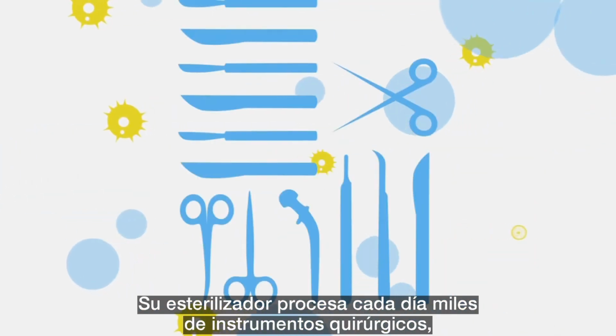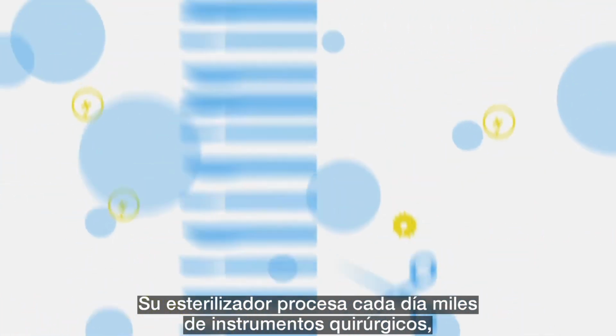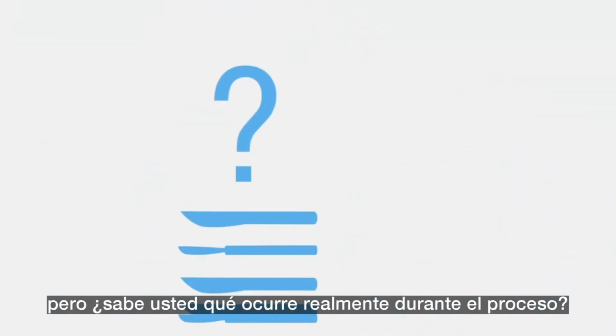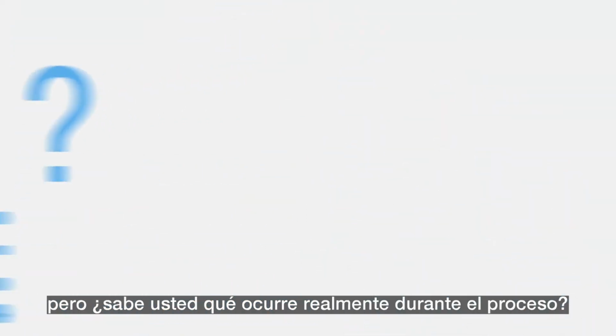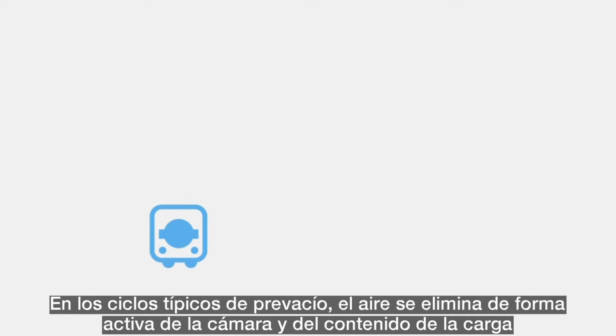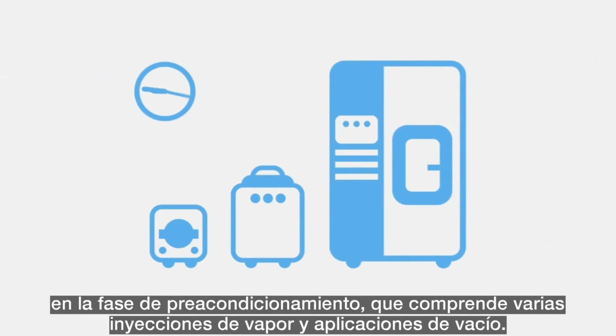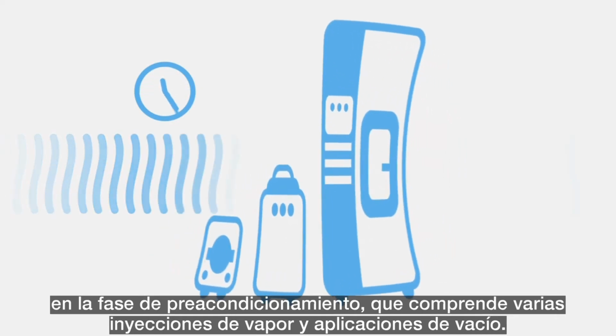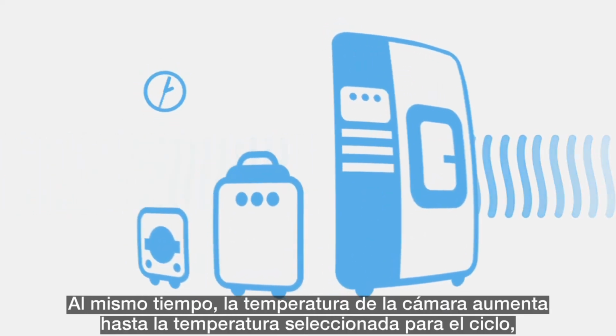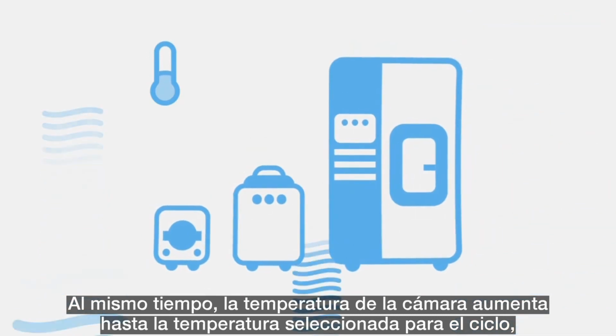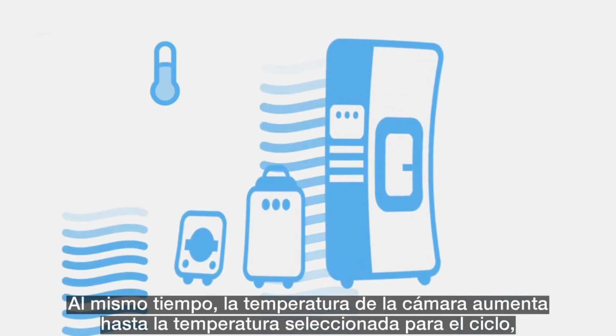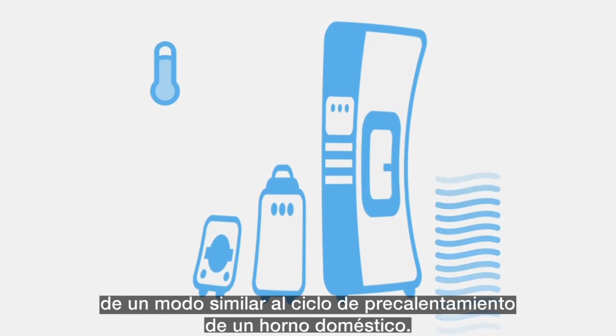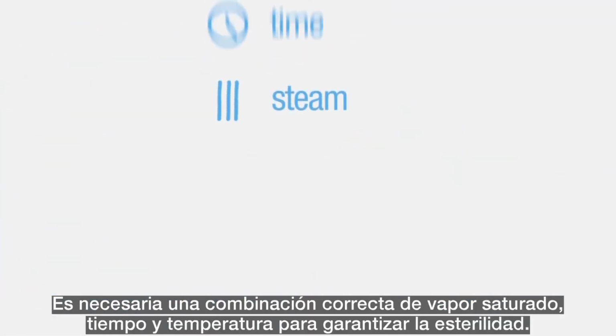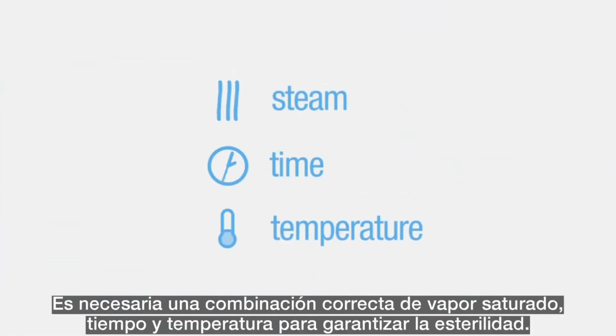There are thousands of surgical instruments processed in your sterilizer every day, but do you know what actually happens in there? In typical pre-vacuum cycles, air is actively removed from the chamber and the contents of the load during the preconditioning phase, which includes a series of steam injections and vacuum pulls. At the same time, the temperature in the chamber increases to the selected cycle temperature, much like the preheat cycle in your oven at home. The right combination of saturated steam, time, and temperature are needed to ensure sterility.